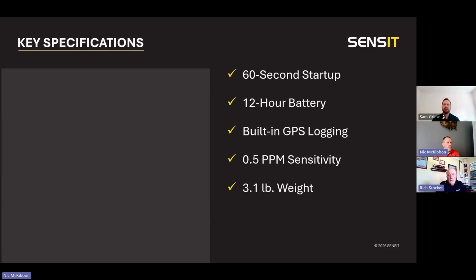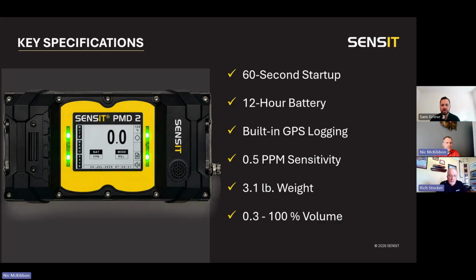One of the key aspects of the laser-based technology is a very fast warm-up time. We're at a 60-second startup as optics have filtered into the industry and have slowly been replacing flame ionization technology and other technologies for sensing low-level gases. The big advantage of the laser is, first of all, the speed in which it warms up. If anybody's used the infrared absorption spectroscopy technology in the past, our previous generation PMD instrument utilized that. It could take up to 12 or even 15 minutes if the instrument was left out on a vehicle in the cold weather to get up to critical temperature and then to zero. So we're very, very quick as far as warm-up time goes.